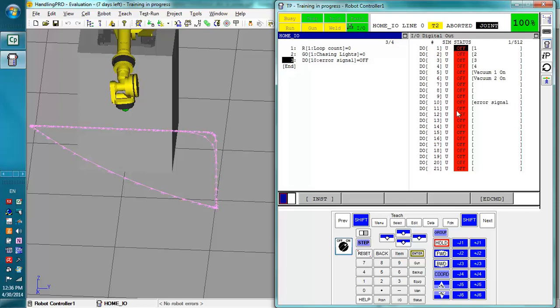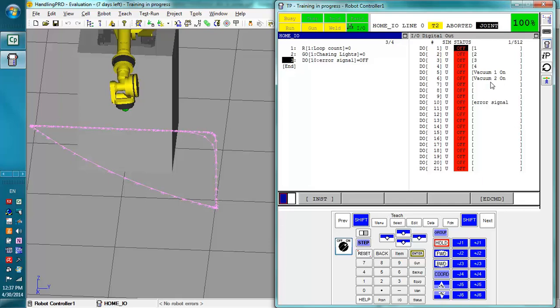Or if you have a bunch of digital outputs that are alarms, and you can set them all into one group. And then when the PLC sends the reset command in a program, you can just set that group output to 0. And that way it clears all the digital outputs that are on. Those are some of the uses for this. It can also be used to control vacuums. If we had four vacuums right here, and the vacuums we turned on would vary from program to program, rather than going through every program and changing which digital outputs go on, we can always just have it say group output 2 for vacuums will turn on all four or just two as needed in the program.